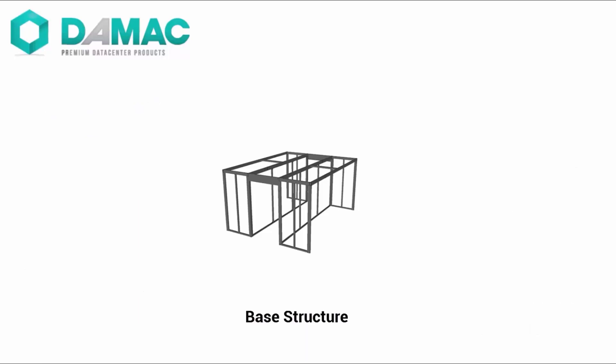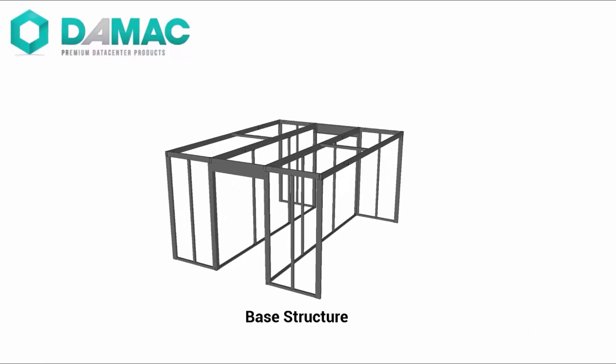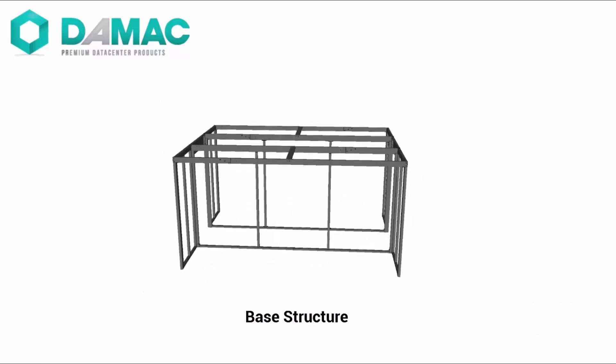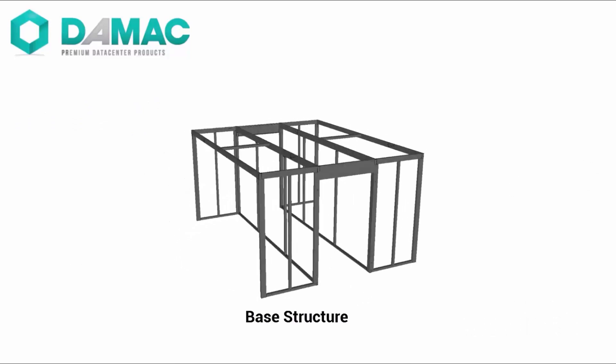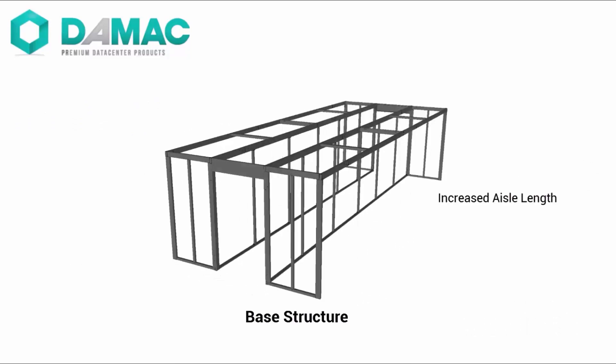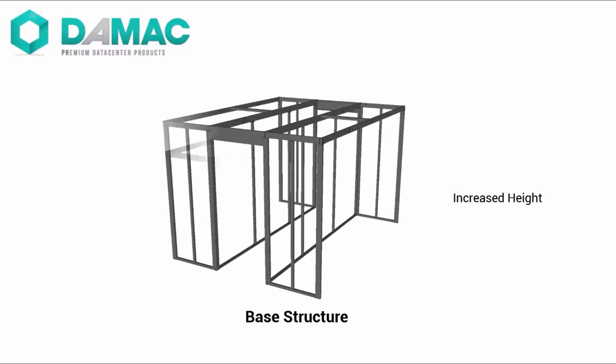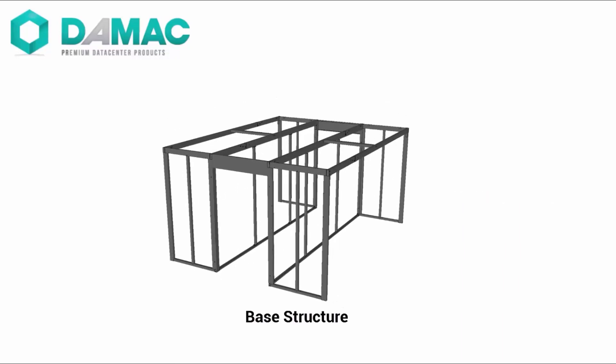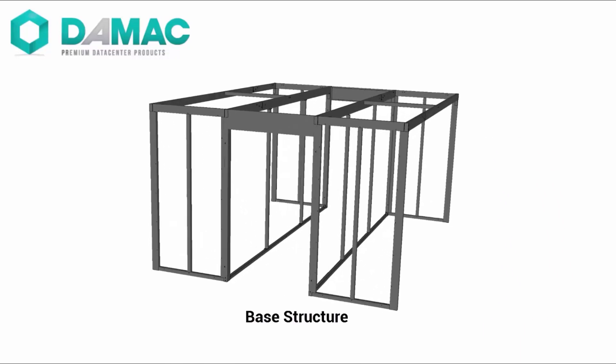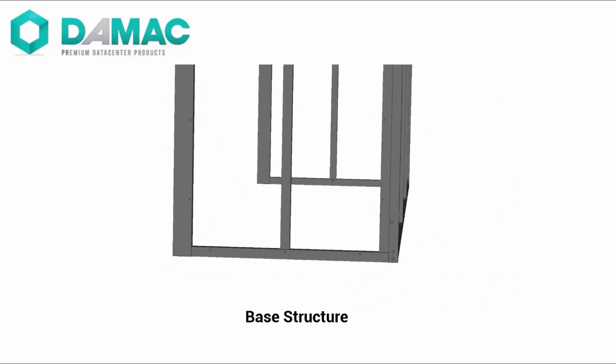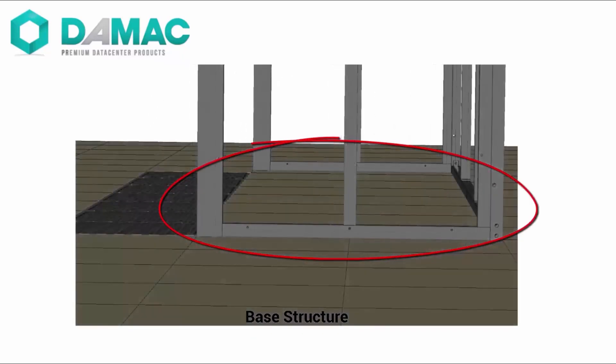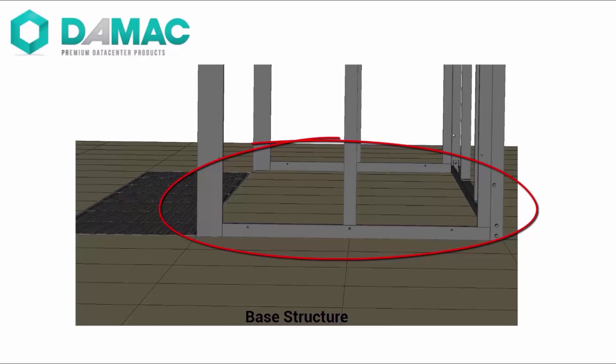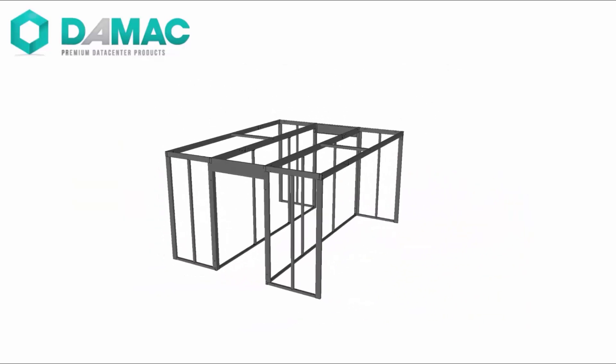The base unit of the DAMAC structure system creates a self-contained cabinet anchoring and aisle containment platform. The base unit can be designed in any length, width, and height to accommodate the physical environment and the racks and cabinets to be installed within it. The base unit has built-in anchoring provisions for server cabinets and racks, eliminating the need to anchor individual racks to the concrete slab or raised floor.